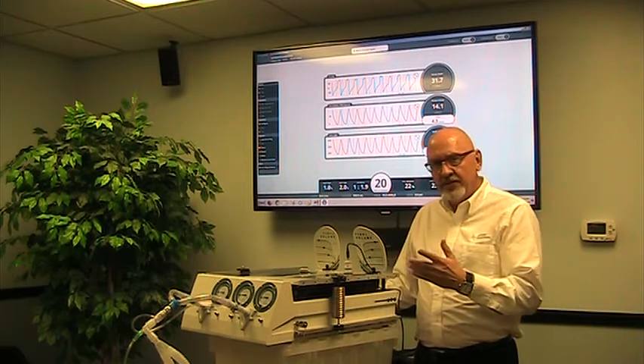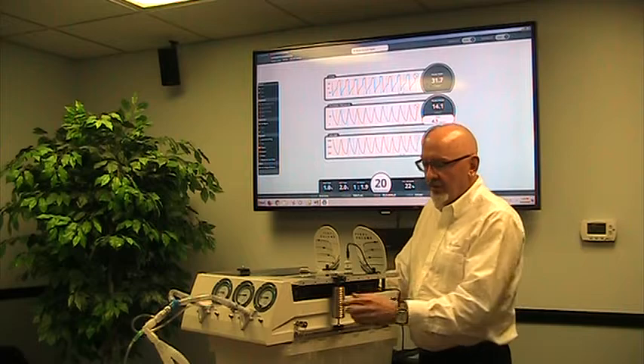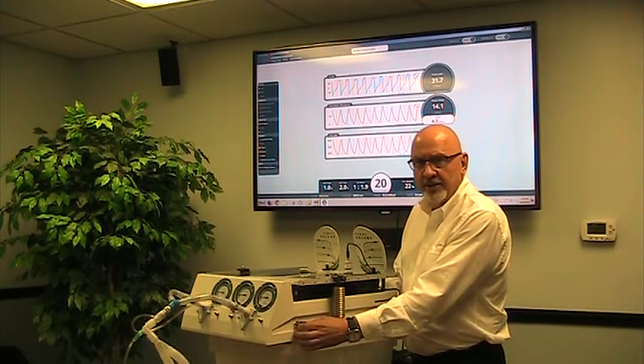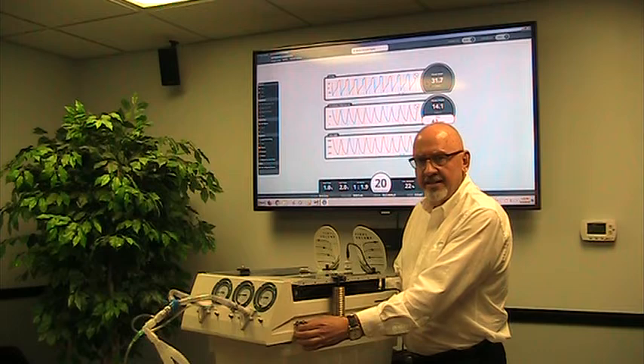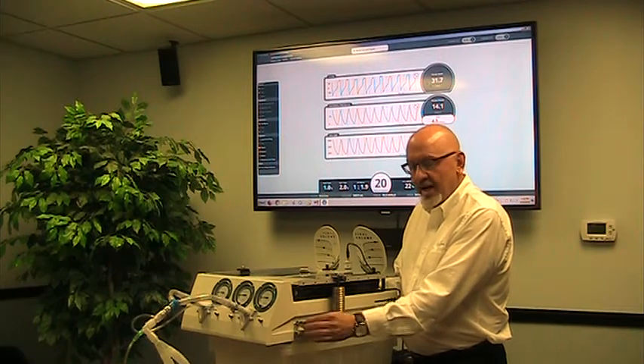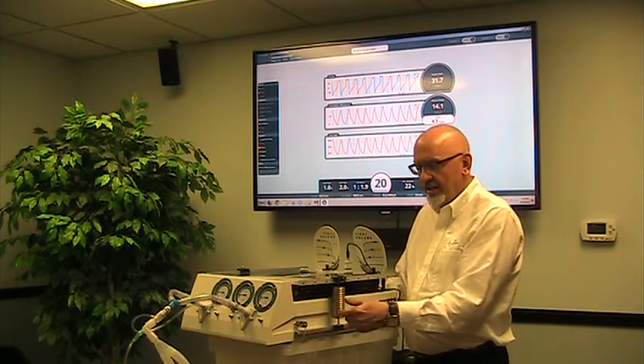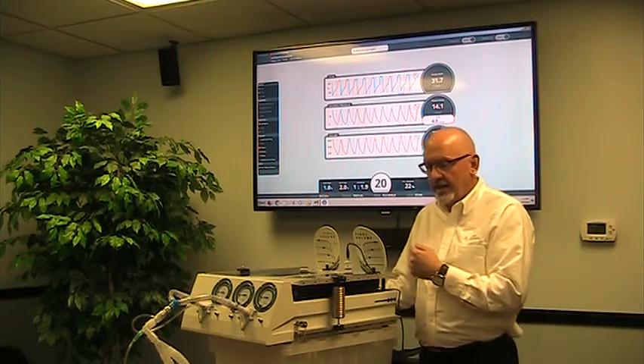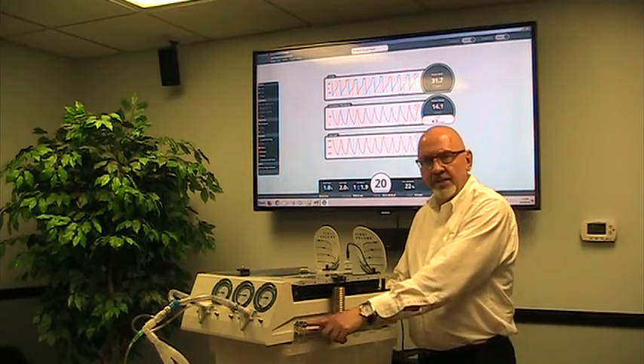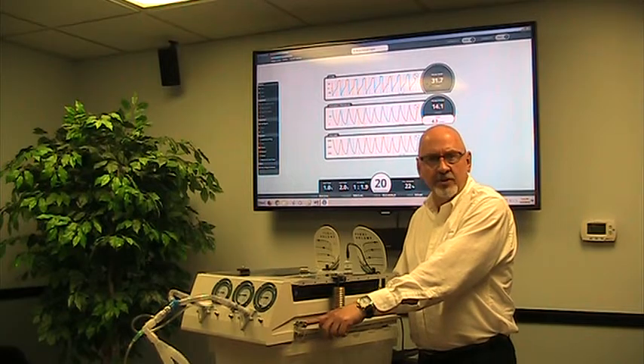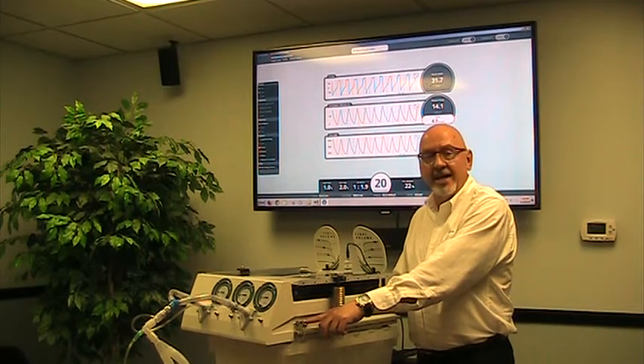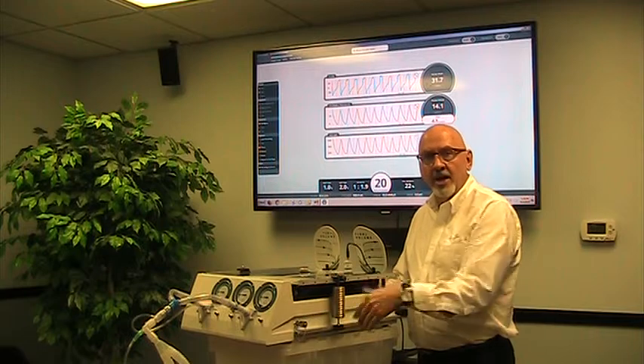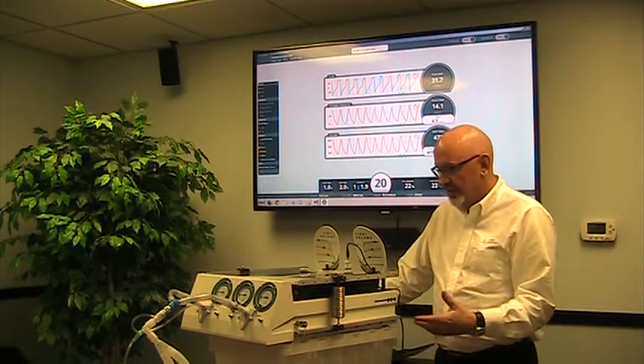With NuView systems we have added a port for high pressure. This is something that's not on the TTL training test lungs. We added that because we can look at high pressure measurements using the software and that allows you to look at wall source supplies or gas regulators and make sure that they are outputting at the desired pressures.